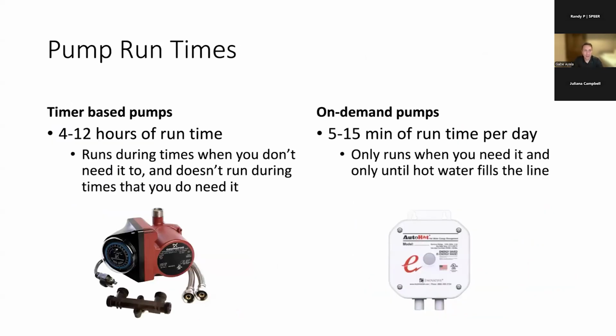Timer-based pumps typically run anywhere from 4 to 12 hours per day. And then an on-demand system typically runs for only about 5 to 15 minutes of runtime per day. And again, it's not just from the energy standpoint, but it's also important to stress how damaging circulation flow can be to your plumbing system over time.